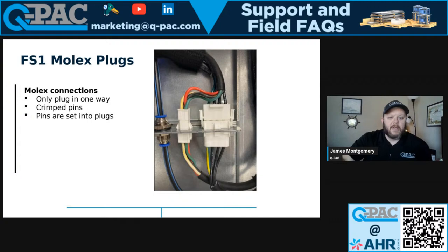Moving on. Next thing. So the beauty of the Q-PAC system, the ease of install, if you've attended any of these before, is yes, you need your electrical contractor to connect your high voltage to your control panel, and coming out of your control panel to your quick connect box. But once that's done, the rest of this is plug and play. And so what you're looking at here is, I told you about that ledge. To the right of each fan, we've got these plug locations. You'll see an air port on the left, the control wire, which is a four conductor control, and then you'll see the high voltage power with the ground. So three phase with the ground. Those plugs are designed to go in only one way.